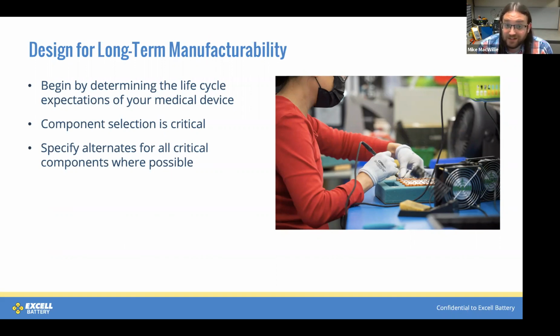There are generally two questions to ask early in the design cycle: how long is the device intended to be sold into the market, and how long will replacement batteries need to be available to support the product after it's no longer sold? In our experience, that can be quite a few years after the end of life of the product. So making sure the battery is able to be manufactured for that entire duration is very important.